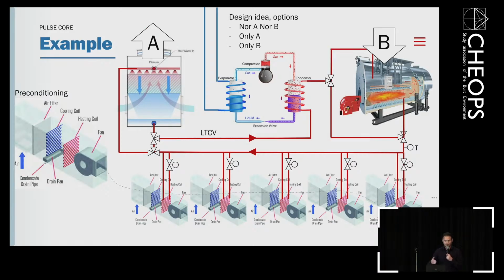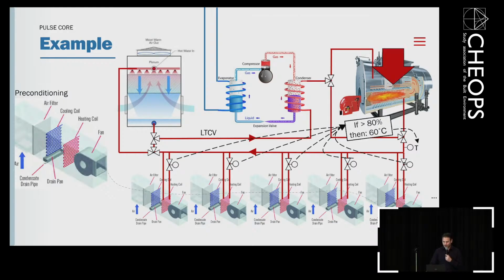The design idea was that we use neither A nor B, because all the heat is used in the air handling units, or we use only A or only B. That's the design idea. The control strategy was very simple: when one of these valves was opened for more than 80%, then the boiler kicks in and would regulate the temperature to 60 degrees.